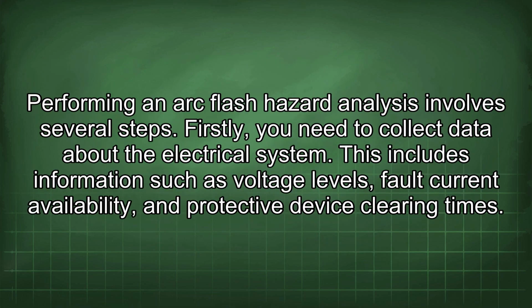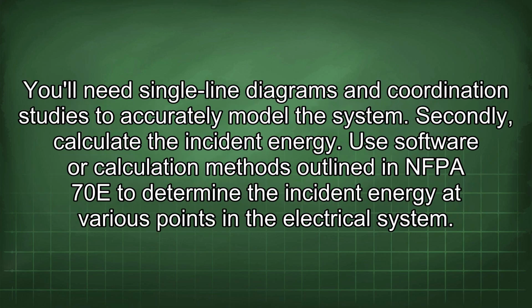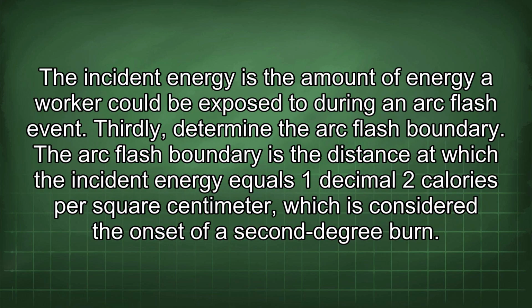Performing an arc flash hazard analysis involves several steps. Firstly, you need to collect data about the electrical system. This includes information such as voltage levels, fault current availability, and protective device clearing times. You'll need single-line diagrams and coordination studies to accurately model the system. Secondly, calculate the incident energy. Use software or calculation methods outlined in NFPA 70E to determine the incident energy at various points in the electrical system. The incident energy is the amount of energy a worker could be exposed to during an arc flash event.